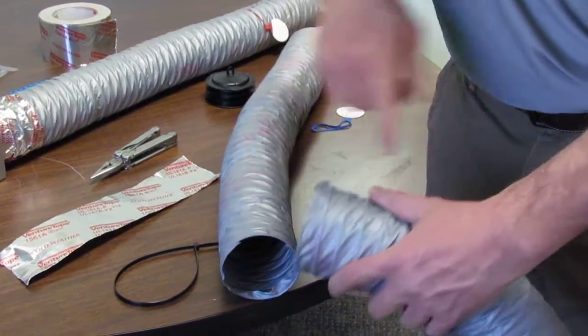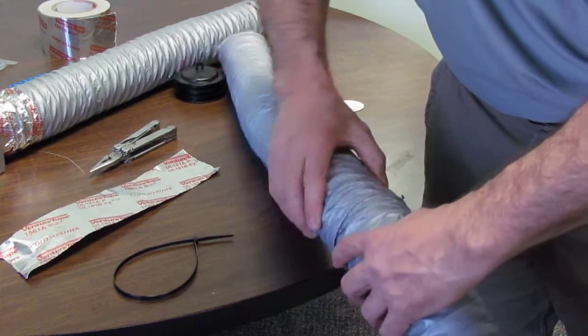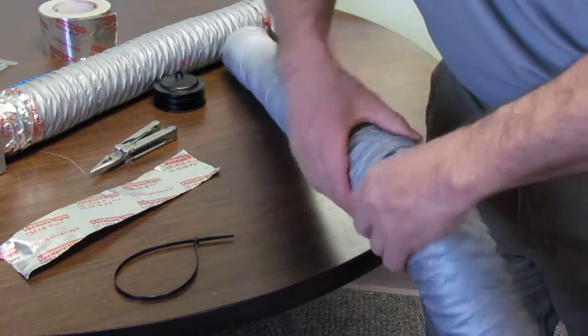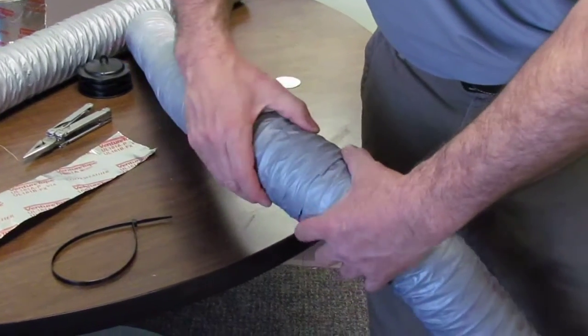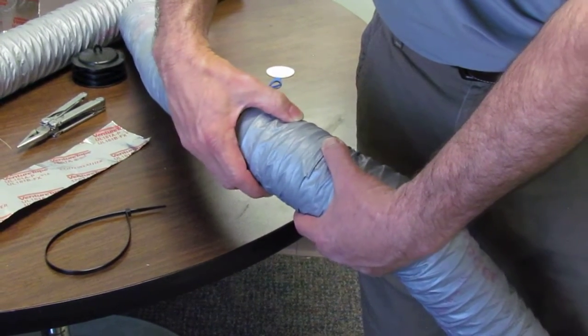Once we have that bend in, if our airflow is going in this way, then this one threads into this one. Just twist it right on. You can feel how far it's going in and you want to overlap by about three threads, approximately two and a half inches or so.